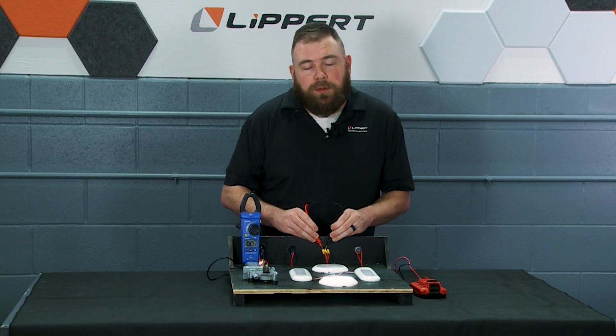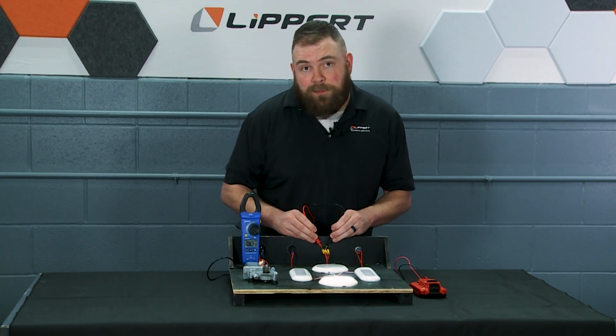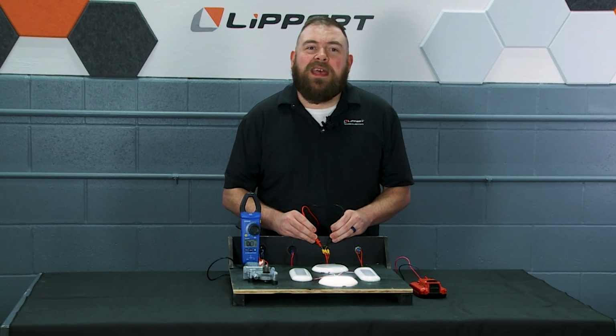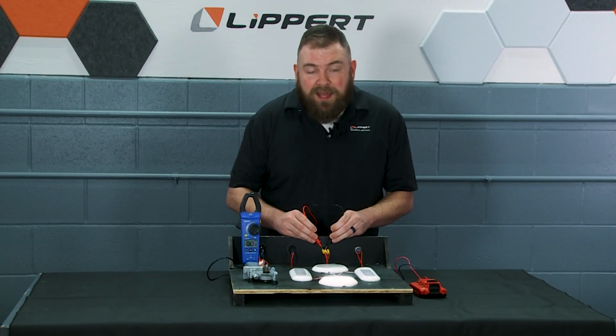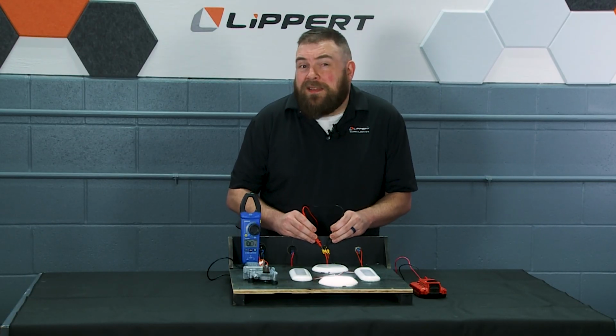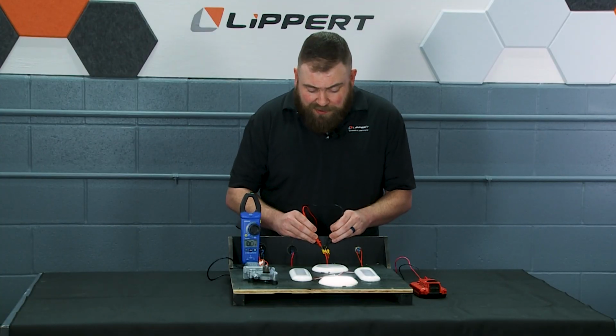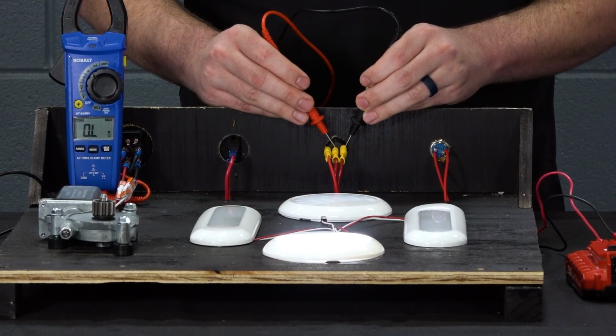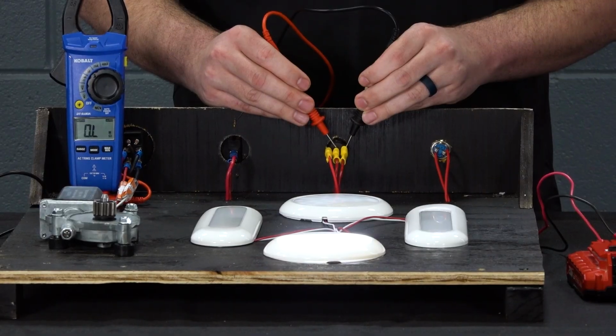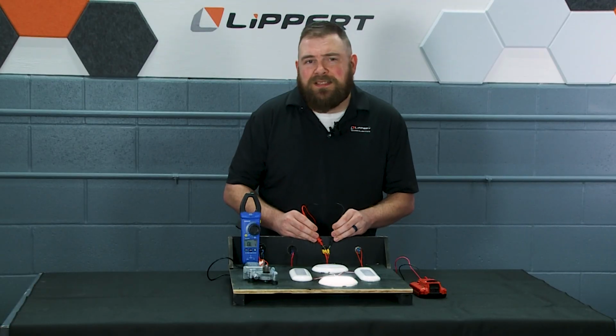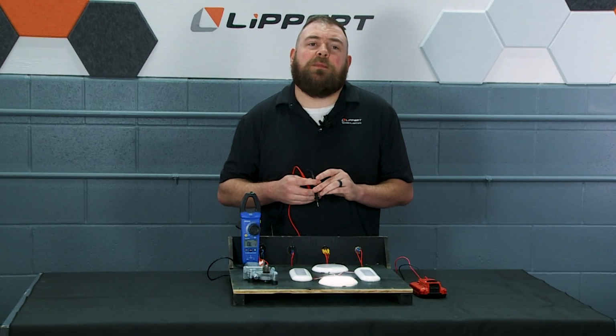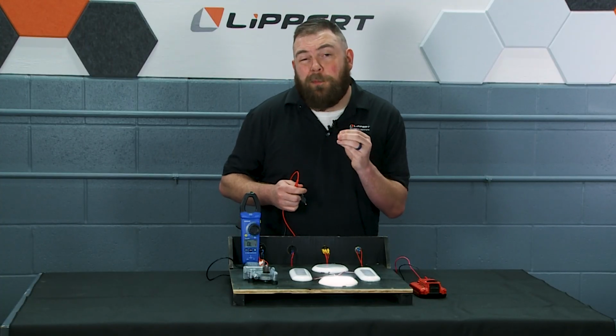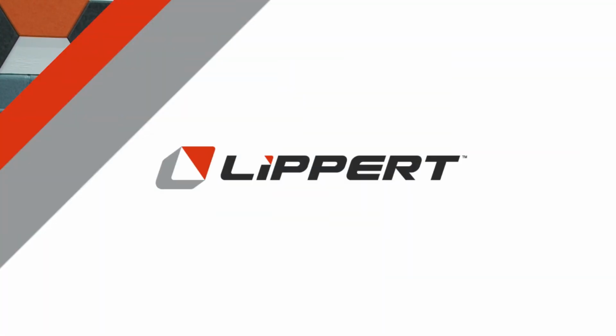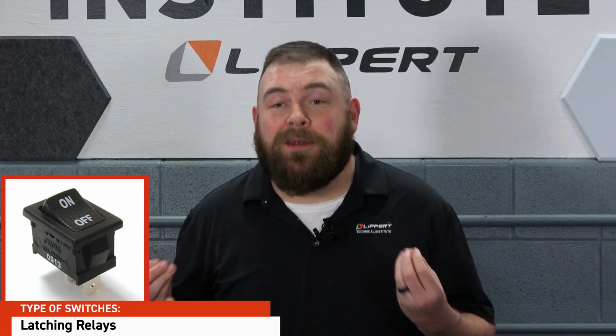We know that we have continuity, but in the instance that it did not come on, this is how we're going to troubleshoot it. If you probe to the same side that you are turning the switch, we might not have any continuity at all, and it would reflect as though I have a bad switch. So keep that in mind. Sometimes the results are mixed, but this is going to be the very best troubleshooting for a single pole double throw switch.